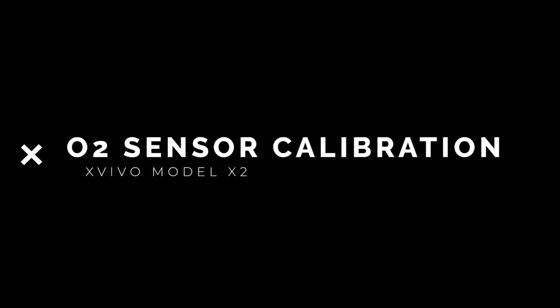Refer to your Xvivo manual for an in-depth explanation of how to check the calibration of the sensors in your Xvivo. In this video, we will demonstrate checking the calibration of oxygen sensors in your Xvivo system. The oxygen sensor's calibration will need to be checked often, at least monthly, because the sensor is electrochemical and the lifespan is only around 1 to 2 years. Therefore, as part of your preventative maintenance plan, it will be in your best interest to keep track of your sensor's health through regular calibration checks.